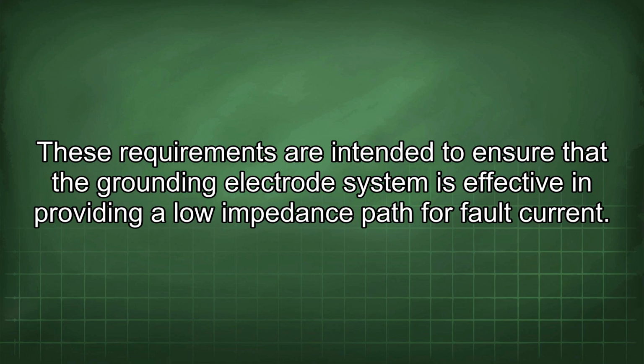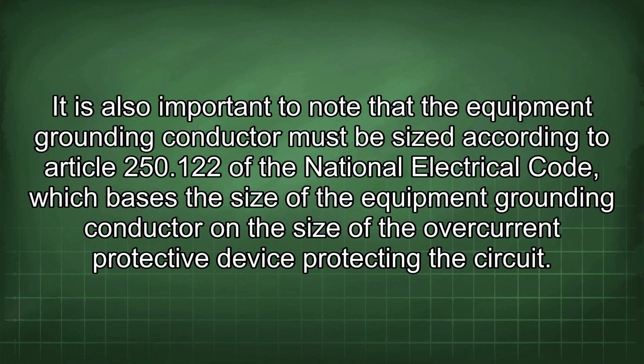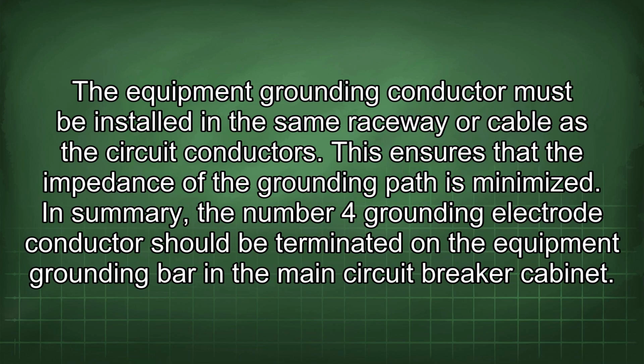fault current. It is also important to note that the equipment grounding conductor must be sized according to Article 250.122 of the National Electrical Code, which bases the size of the equipment grounding conductor on the size of the overcurrent protective device protecting the circuit. The equipment grounding conductor must be installed in the same raceway or cable as the circuit conductors. This ensures that the impedance of the grounding path is minimized.